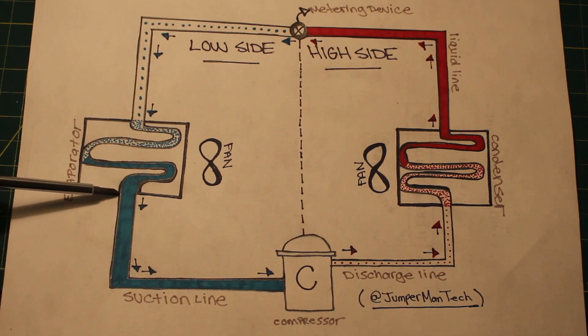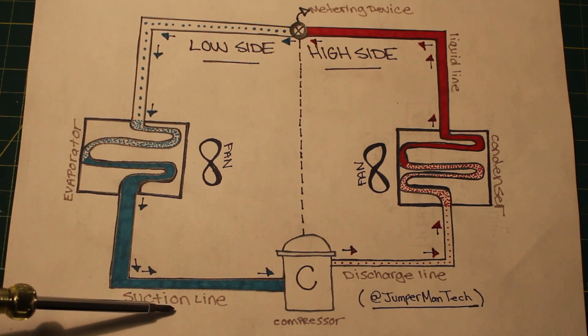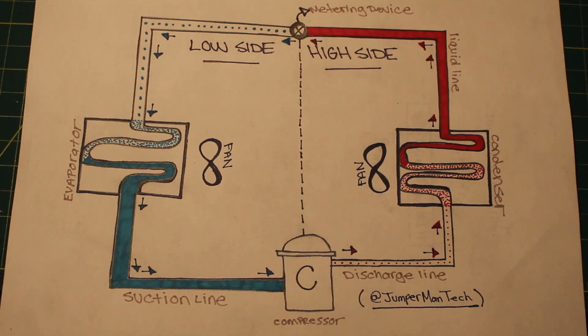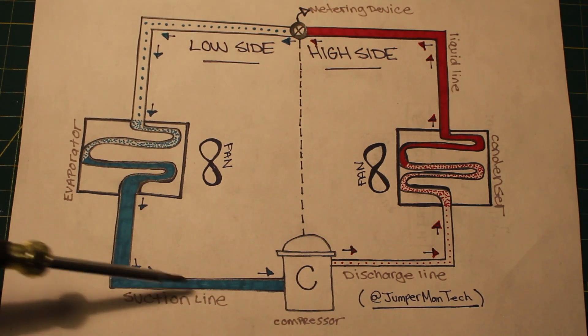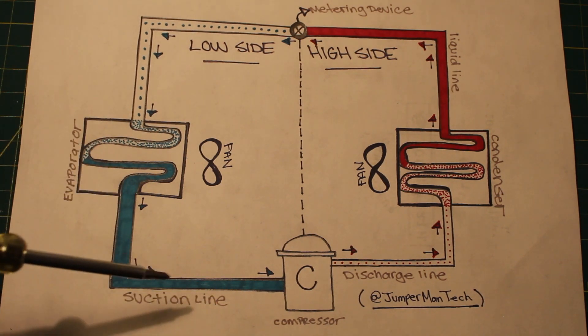As refrigerant leaves the evaporator through the suction line, our refrigerant is now a low pressure, low temperature, superheated vapor. As refrigerant changes state from a liquid to a gas, which occurs midpoint here, this will be our saturation temperature. The temperature increases as it travels down the suction line. The temperature difference is known as superheat.